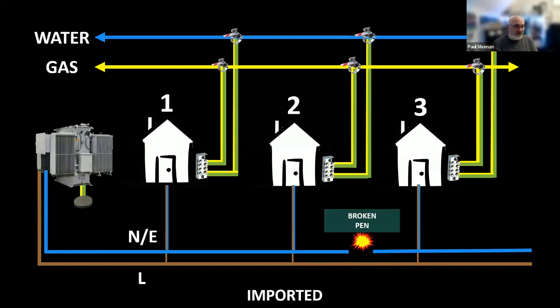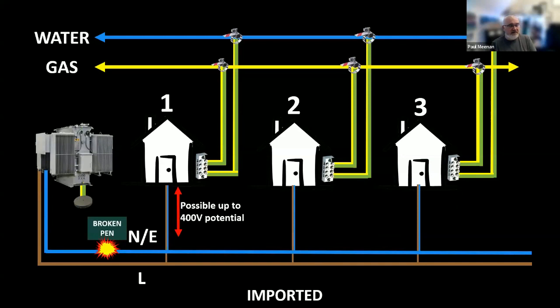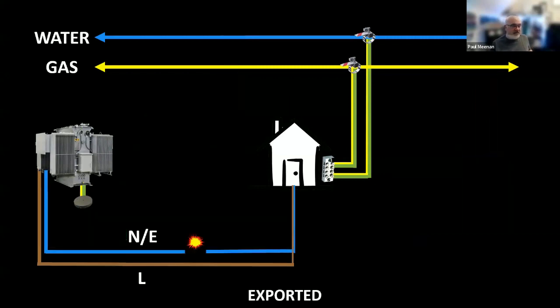And the reason why, I'll show you in a second. Now, what that leads to is, if we do have a broken PEN, you could get potentially 230 volts in house 3 with step or touch potential. So you could go outside, touch your tap and have 230 volts. Further down the line, if you have a broken PEN where you've got multiple houses across phases, you could have 400 volts, which could lead to great injury. And also, if you get 400 volts, you could find your televisions and all your electronics blowing up or failing. So that's as simple as it gets.